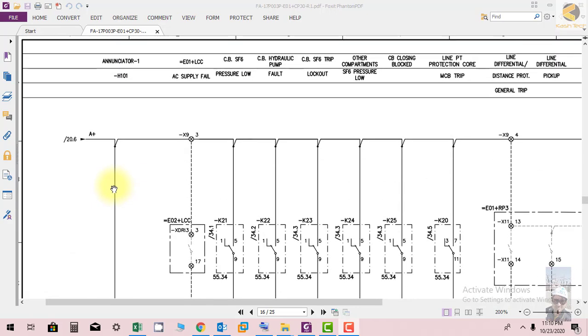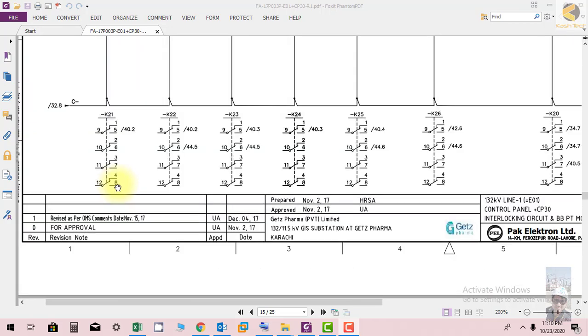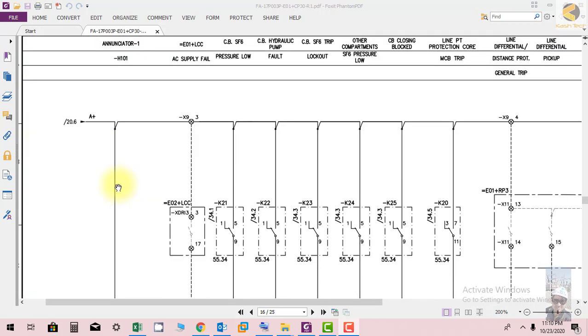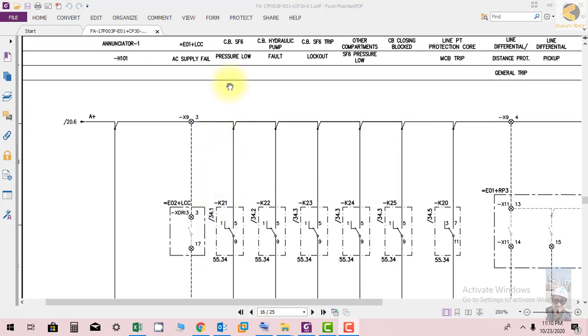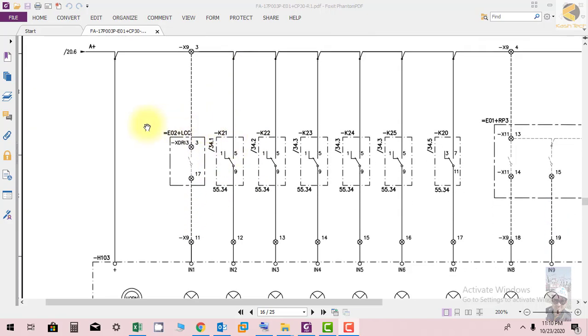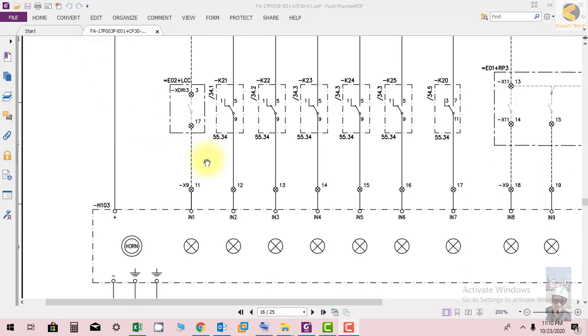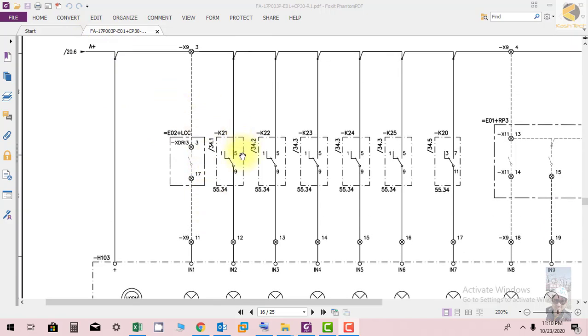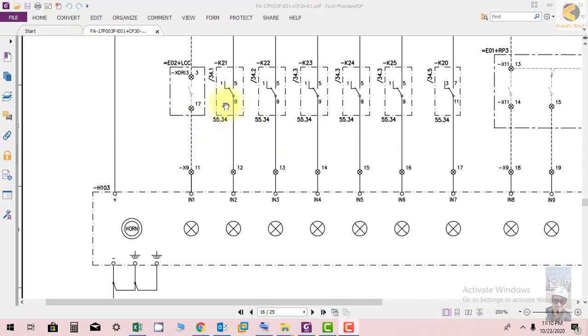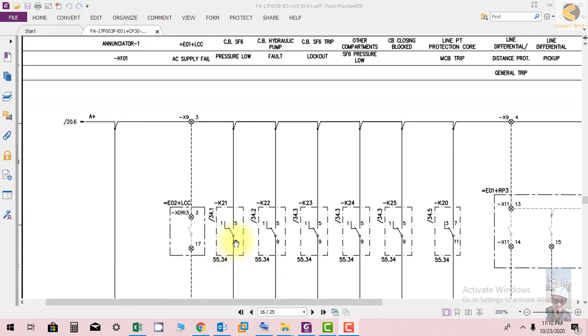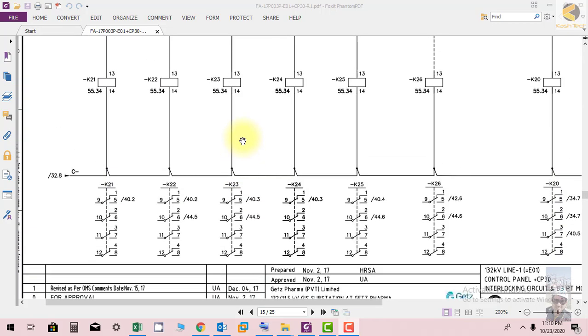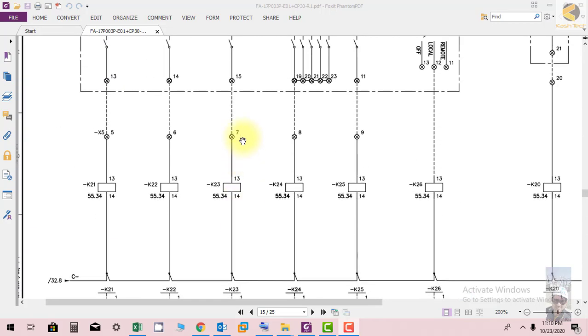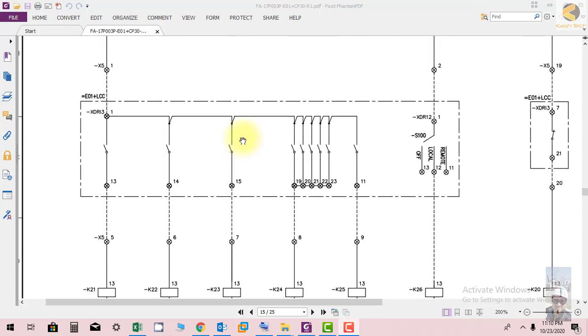On sheet 40.2, K21 indicates SF6 pressure low, and this is the supply for the alarm. When K21 picks up, contacts 5 and 9 will close, and there will be indication and alarm on the control panel that circuit breaker pressure is low.